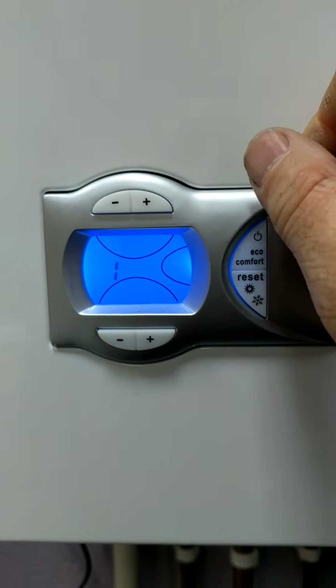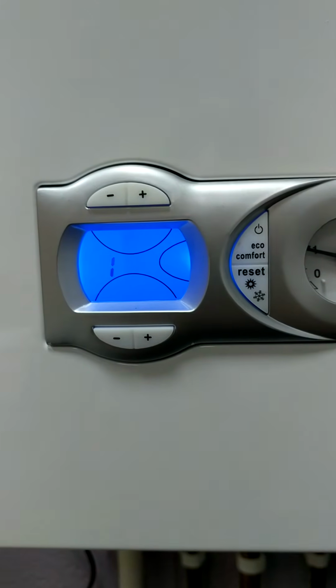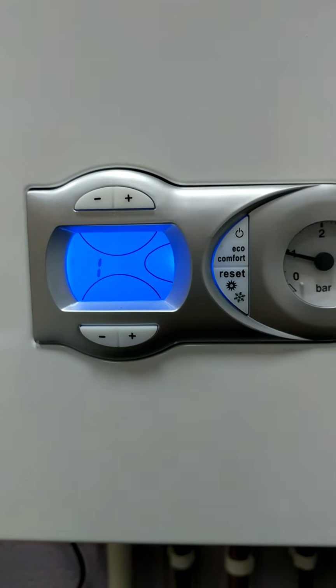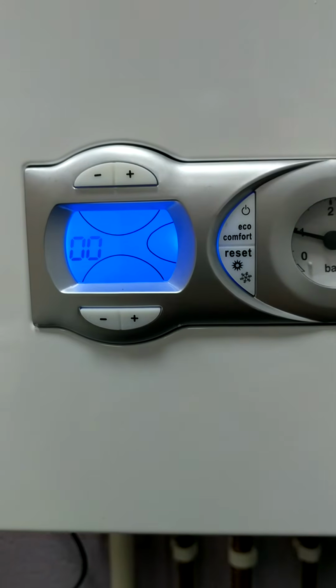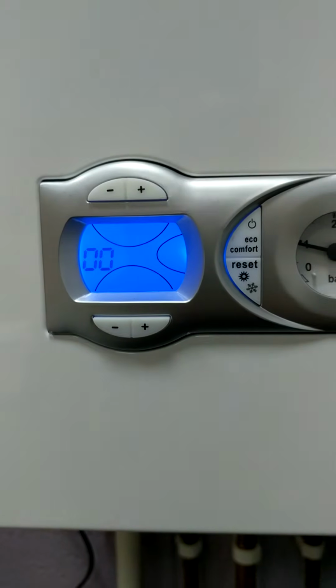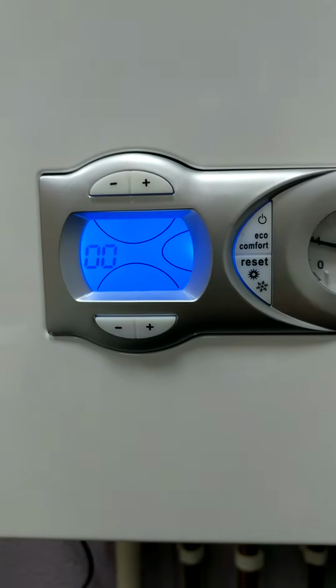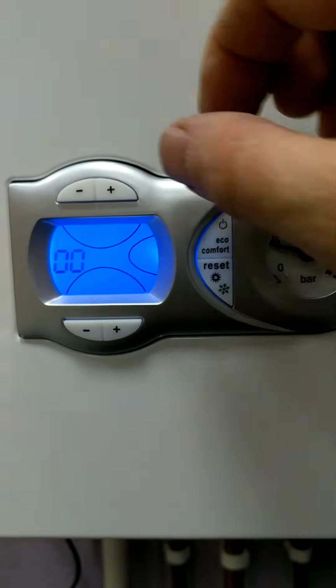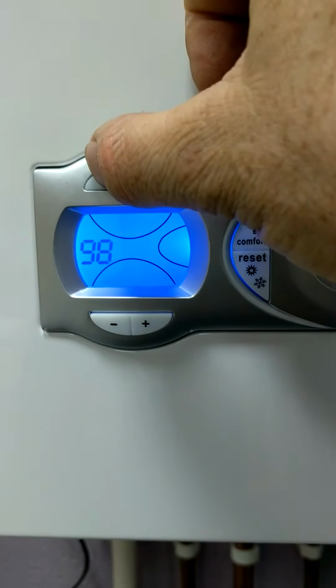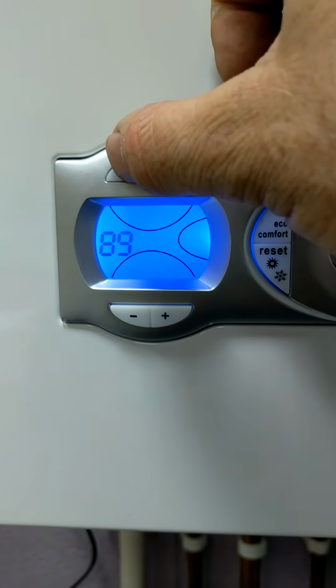And we're going to go to parameter 12, which is the hot water output. And obviously you've seen on the heat exchanger that I showed you, the waterways are that small, you don't really need that type of kilowatt to heat that water up. So we're going to knock this down to 85%.